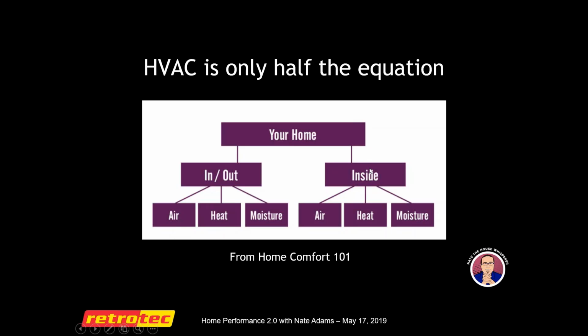Then you can deal with the inside, which is primarily done with HVAC, controlling air, heat, and moisture inside the house. I like how Dave Richardson at National Comfort Institute calls this the house side of the duct system. If the house side is leaky, it's really tough to control. In many cases you don't have to do any more air sealing work, but if you don't test to find out, you don't know. So again, blower doors are critical, critical, critical.